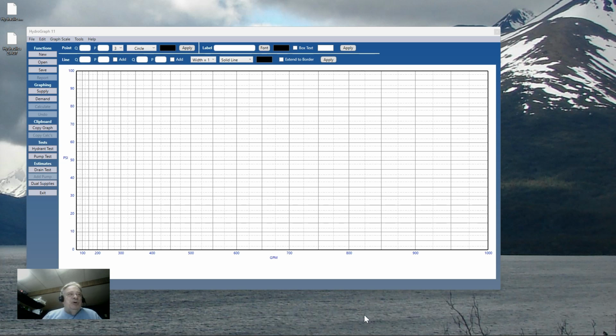Hydrograph's calculations provide a method of evaluating an existing sprinkler system design with respect to an existing water supply. The calculations use the affinity formulas that provide the basis for the graph. Note that Hydrograph is not a hydraulics calculations program. It cannot compare designs of differing design areas, and it cannot compare a density area method design to a CMSA or ESFR design. With that said, let's get started.